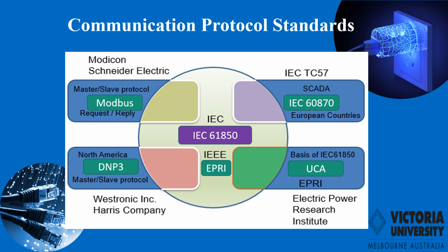The Utility Communication Architecture, or the UCA, is a standard protocol that was recognized all over the electric utility industry in 1988. It shows the successful integration of different electric utility enterprises that facilitated the integration of communication protocols and formed the basis of the IEC 61850 standard. The international goal is to agree on a single standard, and the IEC 61850 standard was born. It was launched in 1997 to develop a communication protocol for substation automation.